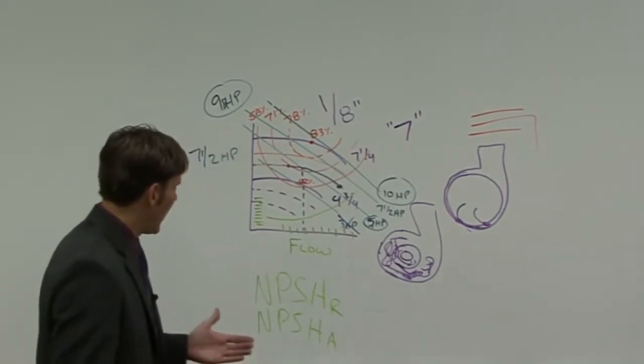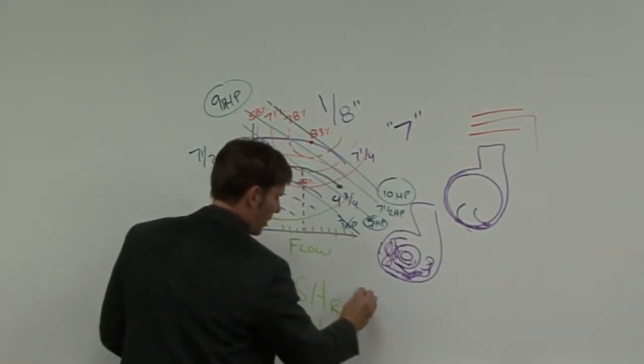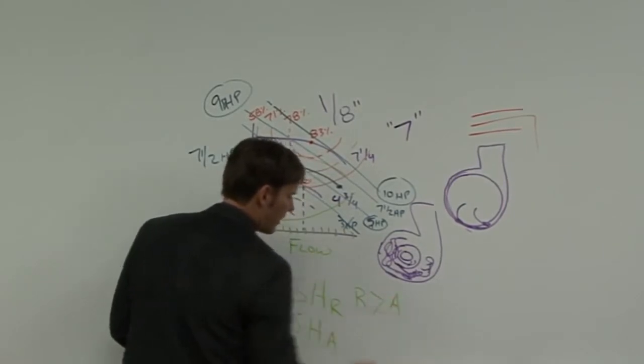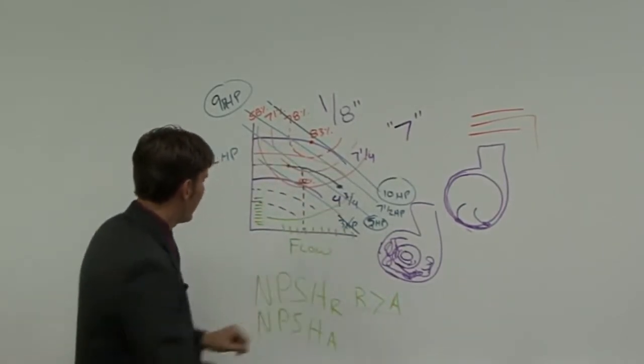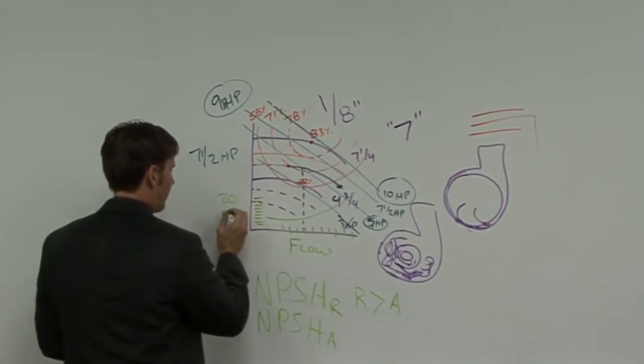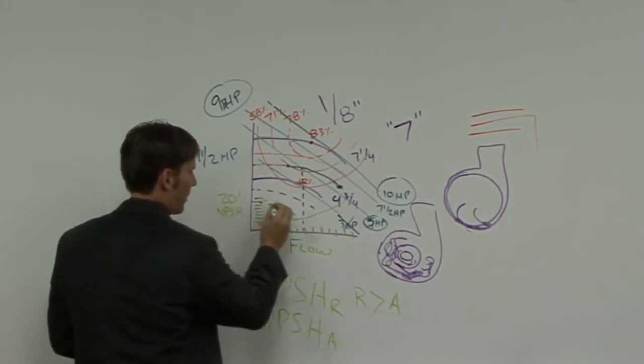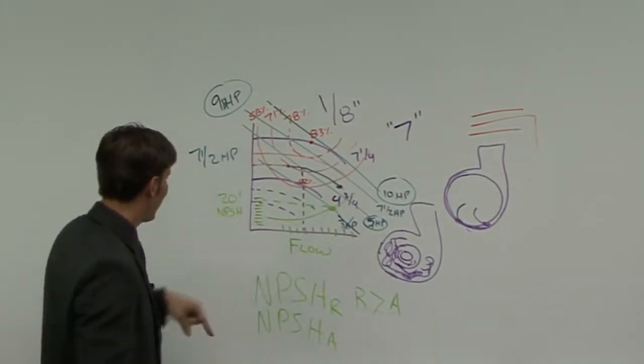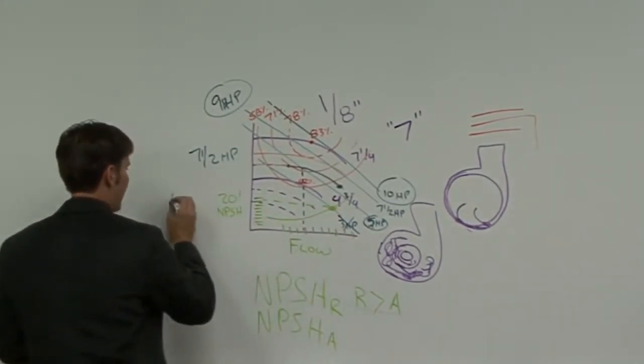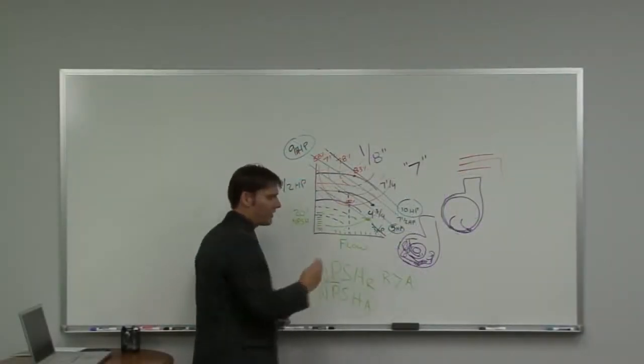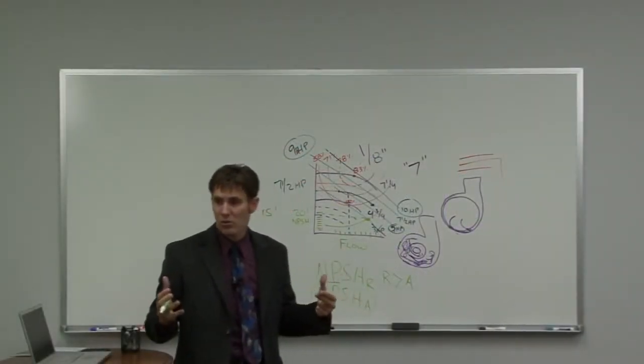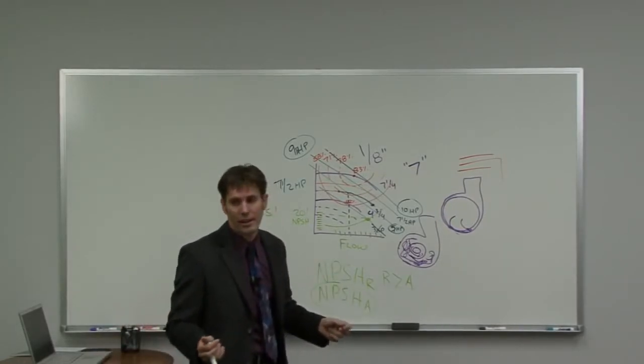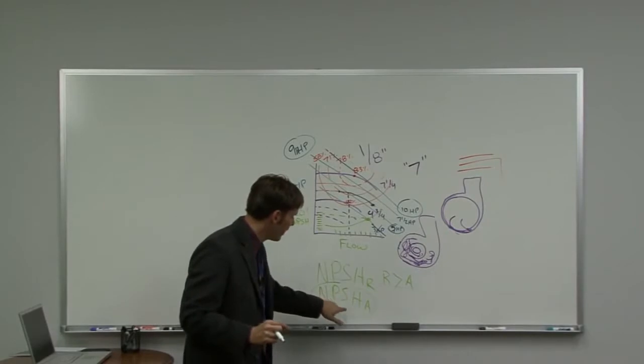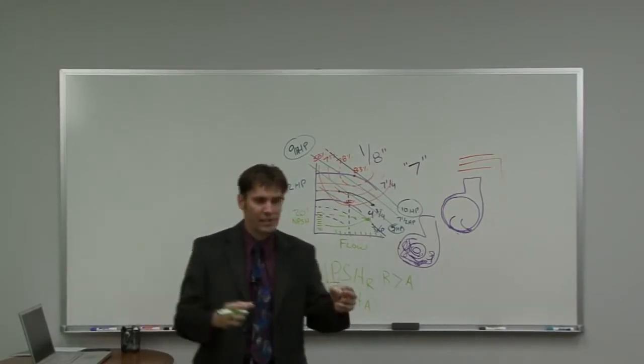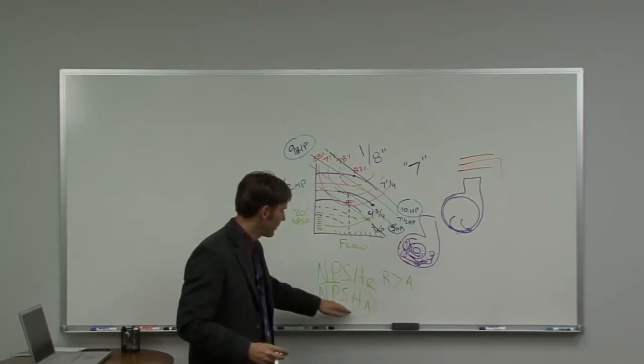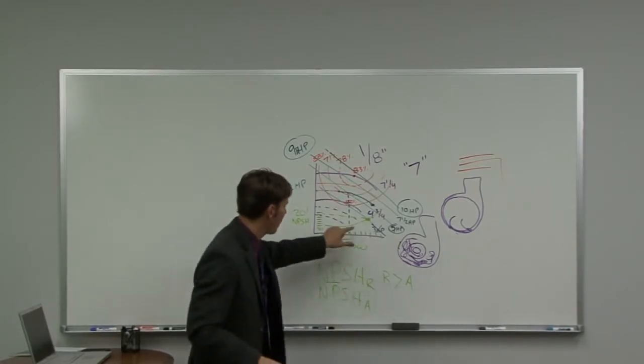Then we're good. However, if my R is greater than A, if what's required, so let's say I need 20 feet of net positive suction head based on this pump curve, but when I run my calculations, I only have 15 feet. It doesn't matter what that water temperature is, it will be boiling. It could be 50-degree water for all I care. It is now boiling because that's all figured into this calculation. Now we do teach other classes on NPSH, so we don't have time to go over these formulas, but it's important to understand that's what we're looking at here.